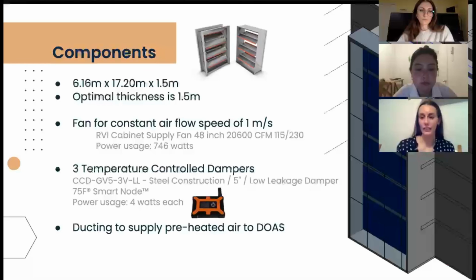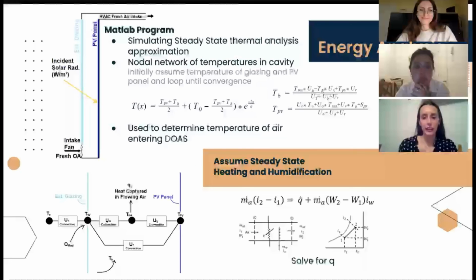The thickness of the cavity is optimized for the largest energy savings. A fan with a constant velocity is used to provide preheated air to the DOAS. Temperature-controlled dampers are implemented in order to allow for optimal tempered air. An energy analysis of the solar wall was modeled using MATLAB through a steady-state thermal analysis approximation. A nodal temperature network was used to determine the temperature of the air being supplied to the DOAS. Steady-state heating and humidification was simulated in order to find the energy savings from providing preheated air to the DOAS.